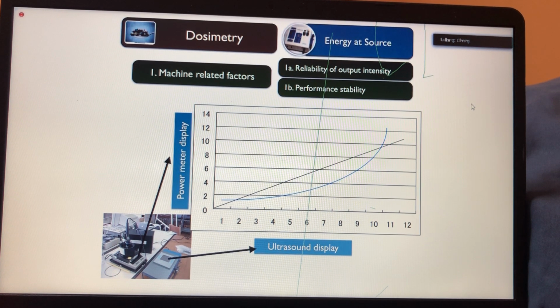And you will know that you don't need to calibrate, but at least you will be able to get the right output based on this graph that you're making. You can get your therapy assistant to make that graph for you every month, for example. And the ultrasound power meter that you need to buy is cheaper than sending it once to the manufacturer to ask them to calibrate for you.